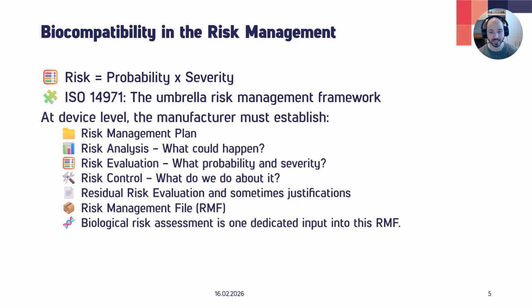So at the device level, we need to establish risk management. We need to establish risk analysis. So what could happen? Then we need to evaluate those risks. So what's the probability and the severity of those risks? Then we need to take measures, risk controls. So what do we do now about these risks? Or do we even need to do something about it? And then we need to analyze the residual risk. And sometimes we need to provide such justifications for that. And then in the end, we have to document everything in the risk management file.